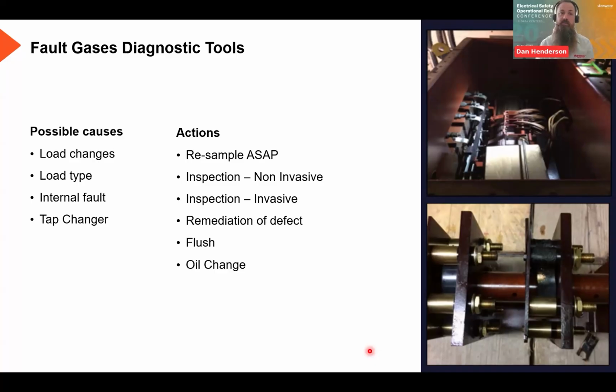This is again someone that I worked with in the past, where they had done the basic fluid samples and then didn't do DGA, and ultimately this tap changer in the bottom right corner failed, and this was a catastrophic failure of the transformer. You'll see there's a lot of carbon buildup on the tap changer. This is inside the oil tank, and right in the bottom corner, this is the termination that went from the HV box to the tap changer. This was blown through. This was another area where we're getting this arcing. So again, if they had been doing DGA in addition to the other tests, this would have been picked up relatively early, and it would have been a relatively simple fix, or at least it could have been identified and planned in rather than the significant downtime that they experienced.